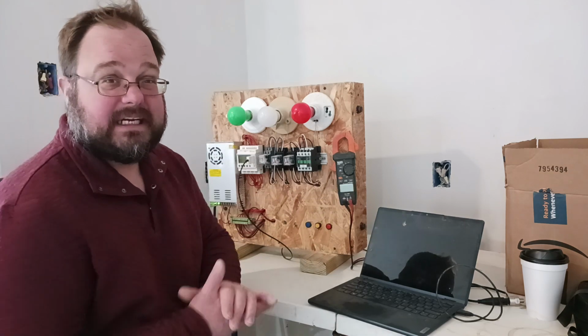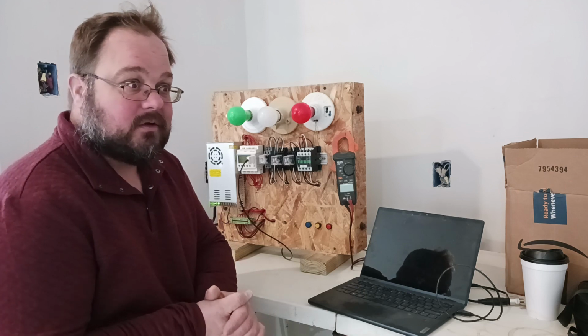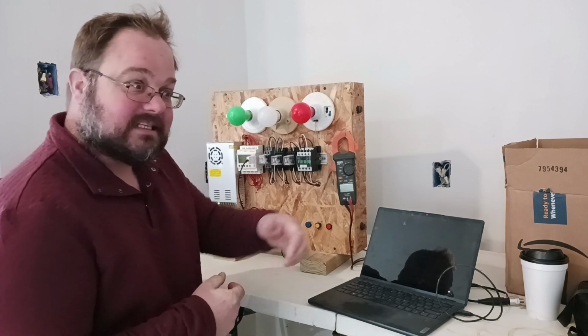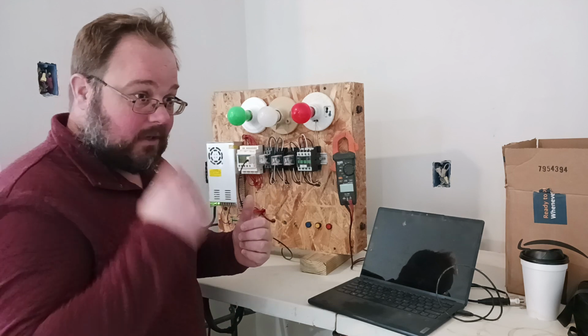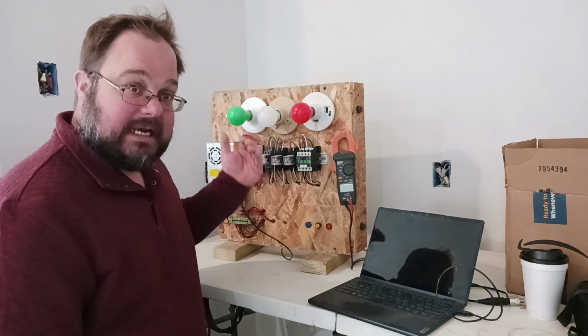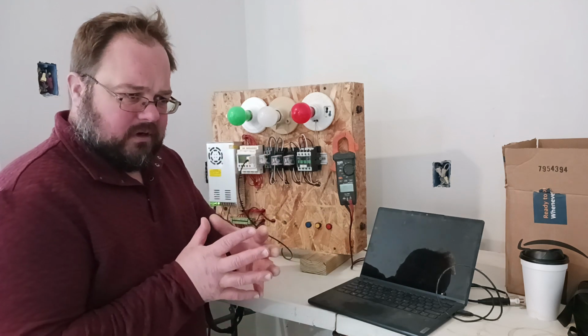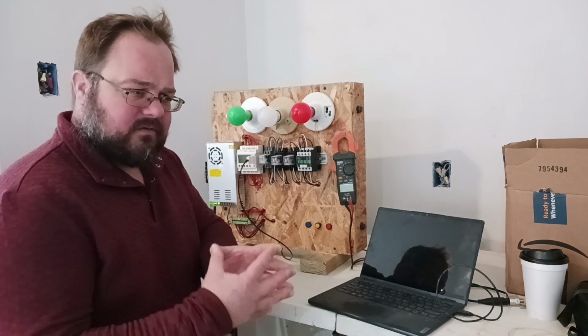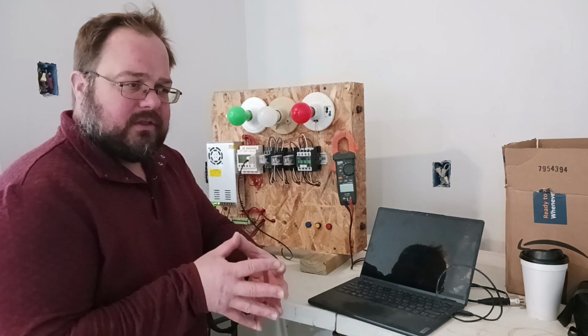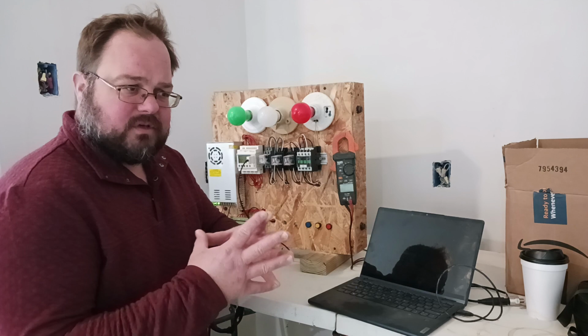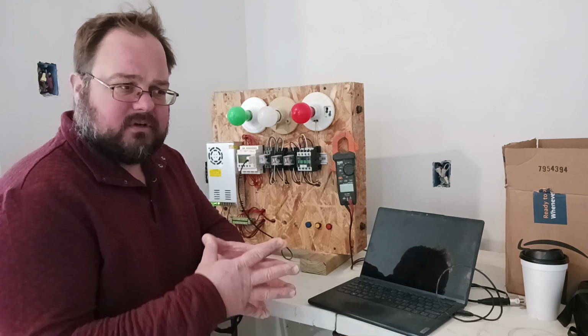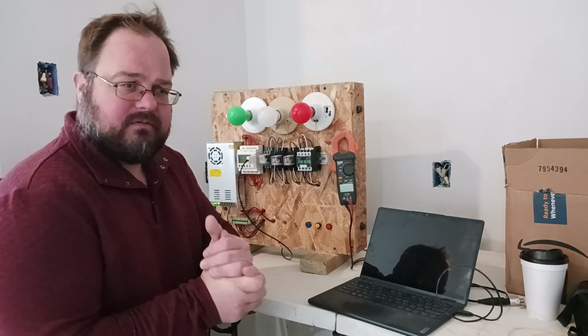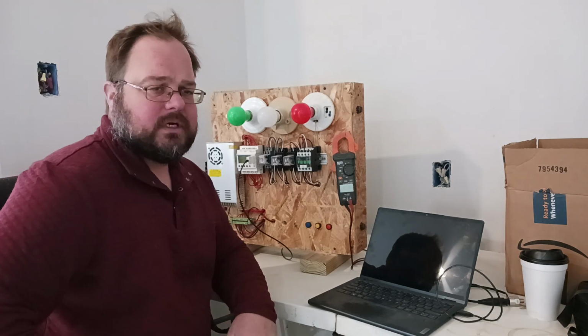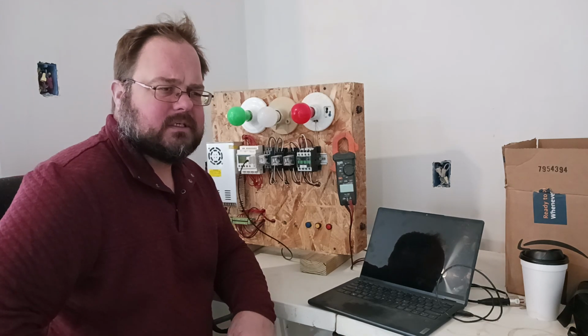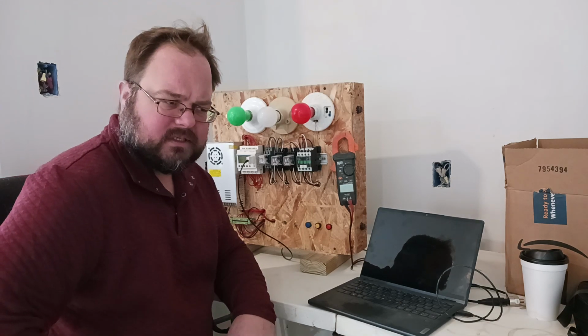If I had what's called an NPN sensor, you probably guessed it - that second N means it sends the signal as a negative, so my inputs would need to be negative. If you're ever troubleshooting a PLC and see positive or negative on the inputs, don't be thrown off if one PLC is wired differently from another. It might have to do with what kinds of sensors people have, and if you have a bad sensor that needs replacing, make sure you replace it with the appropriate sensor.